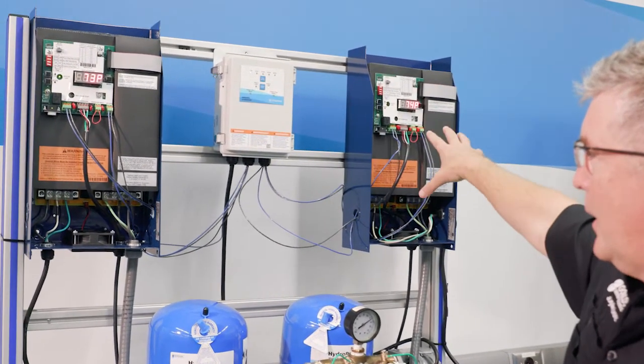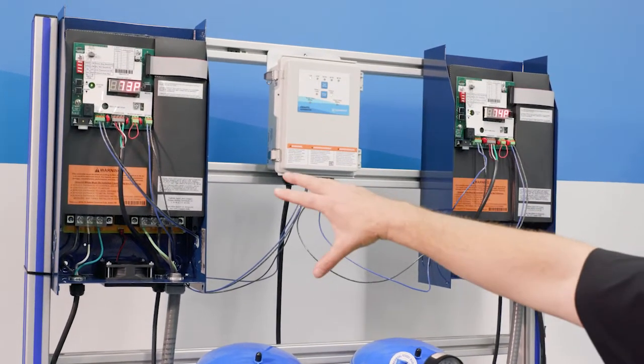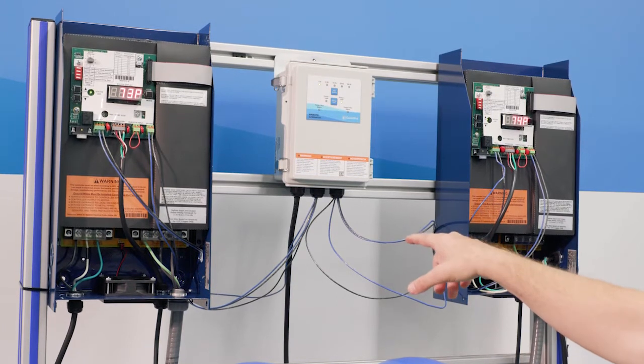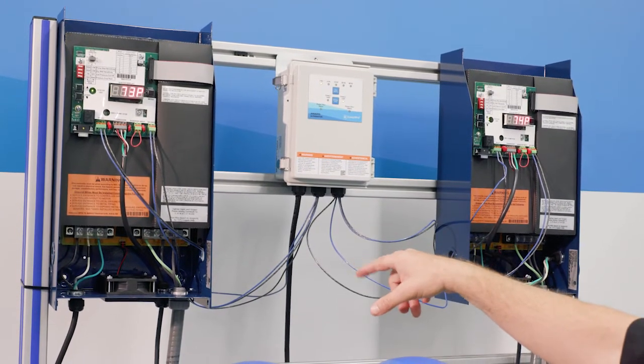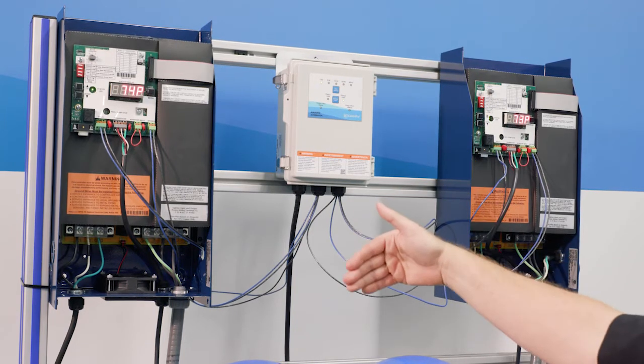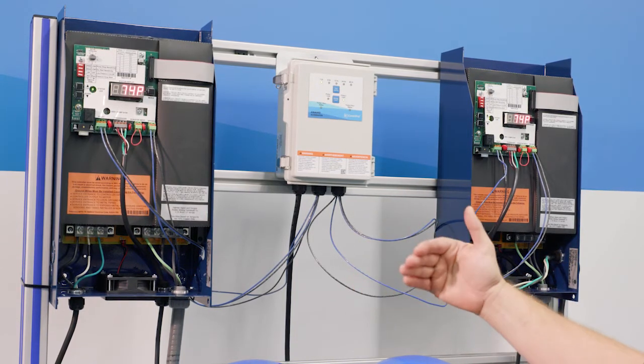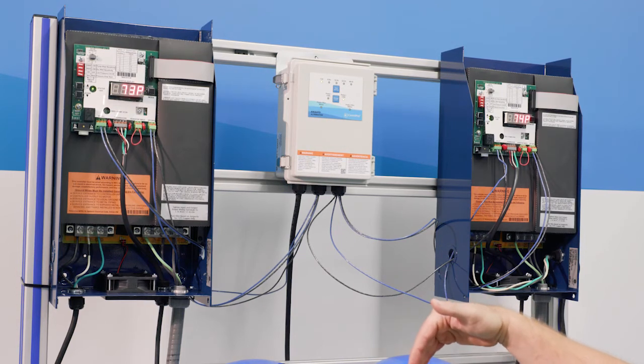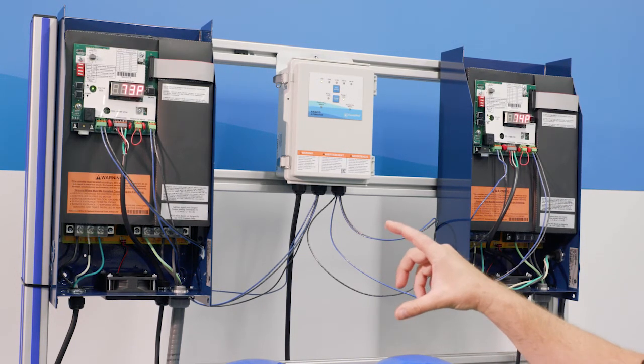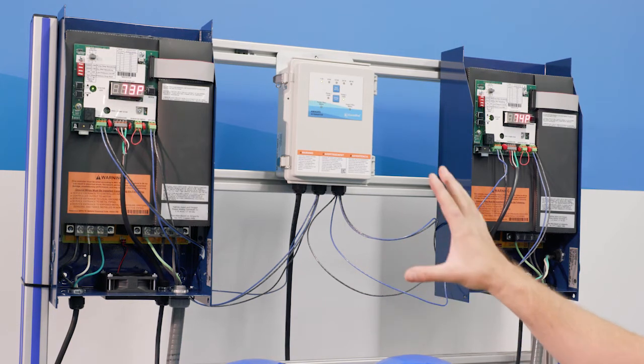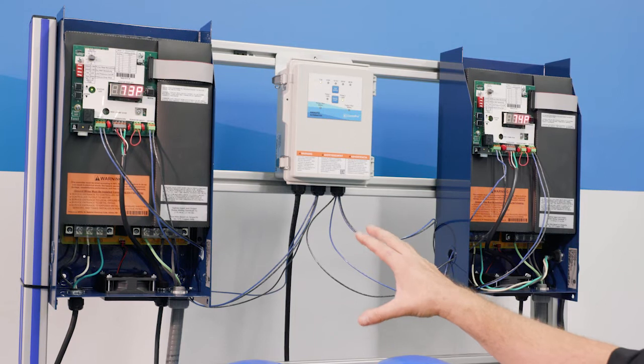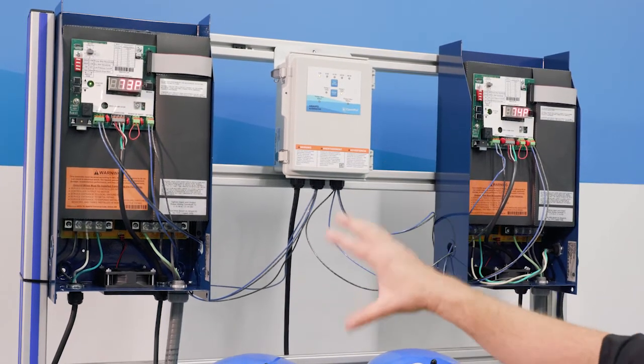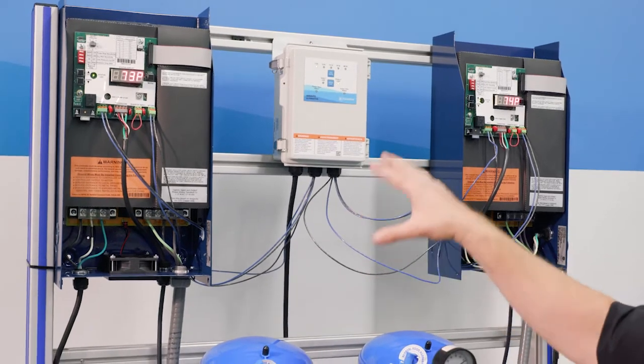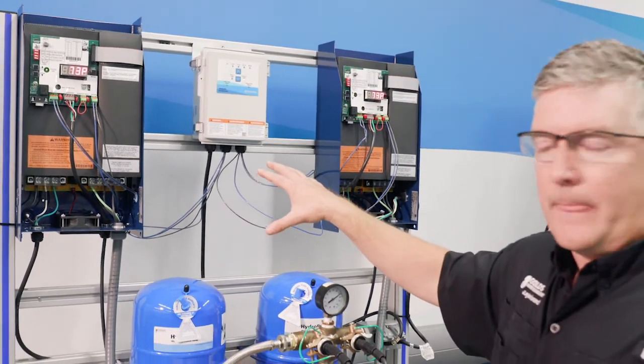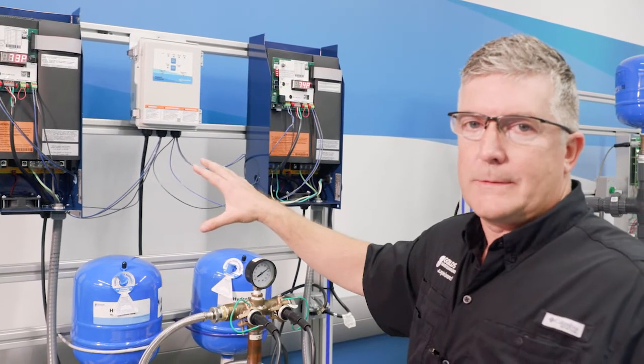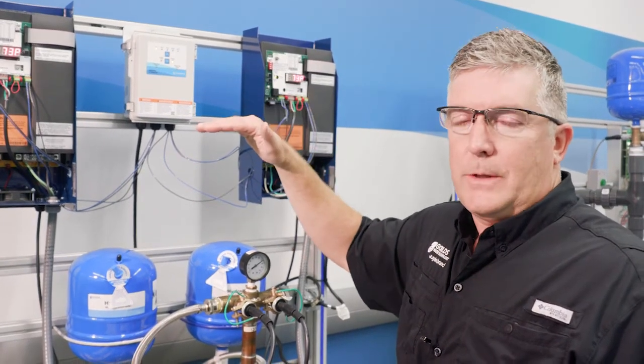Currently we have number 2 as our lead, and number 1 is the lag. We set our set pressures, SP2, which again is our default lead, that's 75. SP1 is the default lag, that's 60. We want at least a 10 psi difference between the two. Now, if you don't like that, you can change that. You can switch those so that SP1 is the lead and SP2 is the lag. There is a procedure in the manual to do that. But out of the box, SP2 is the lead pressure. And again, you want that to be your higher pressure.